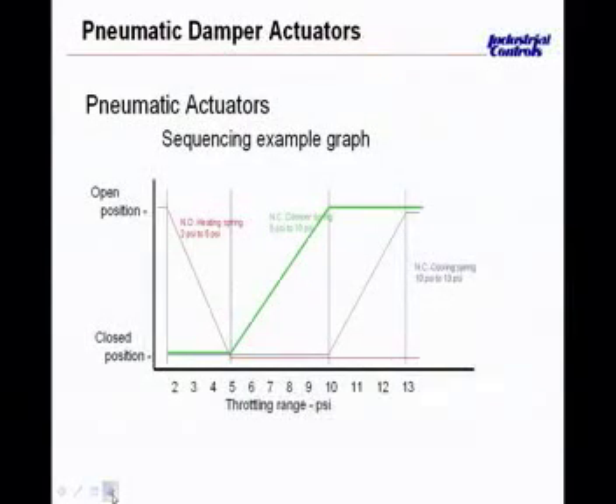So here we see something that looks very similar to what we did before with our air handling unit. But in this scenario, we've got an additional device to sequence. So as before we had just a heating valve and a cooling valve, now we have those very same valves with different spring ranges, but we've added a damper, a cooling damper. So picture that air handling unit with maybe an economizer on it, meaning we can take advantage of free cooling out from the outdoors if it's suitable.